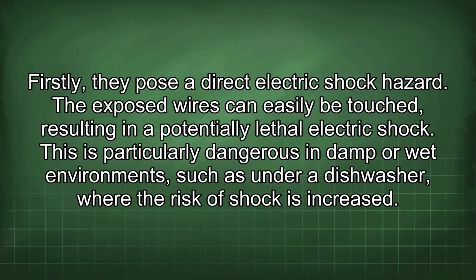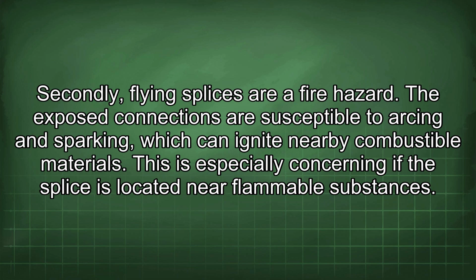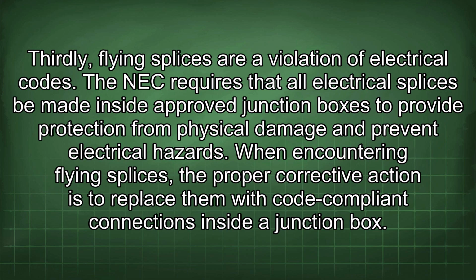This is particularly dangerous in damp or wet environments, such as under a dishwasher, where the risk of shock is increased. Secondly, flying splices are a fire hazard. The exposed connections are susceptible to arcing and sparking, which can ignite nearby combustible materials. This is especially concerning if the splice is located near flammable substances. Thirdly, flying splices are a violation of electrical codes. The NEC requires that all electrical splices be made inside approved junction boxes to provide protection from physical damage and prevent electrical hazards. When encountering flying splices, the proper corrective action is to replace them with code-compliant connections inside a junction box.